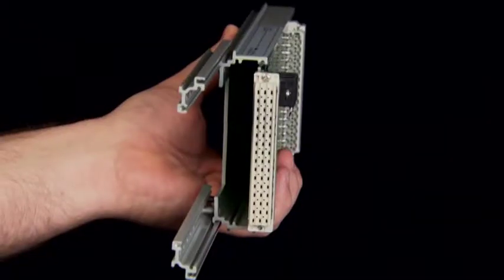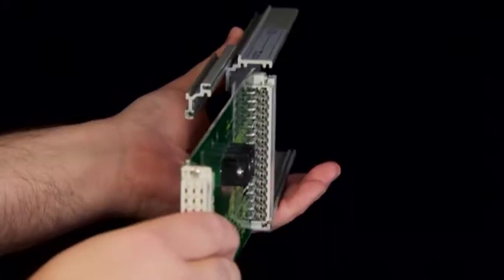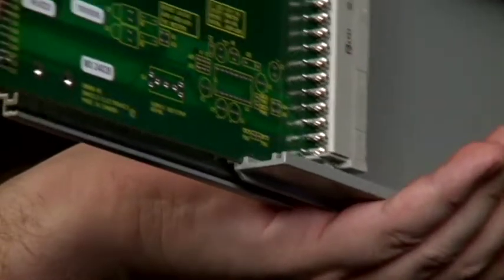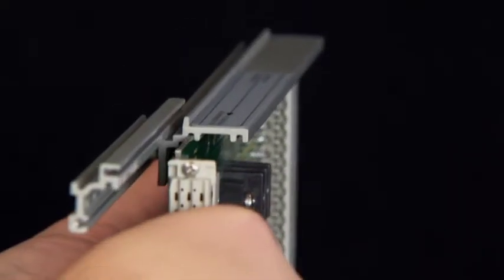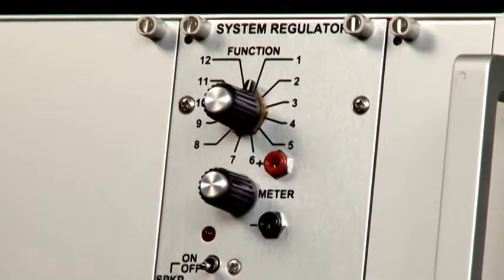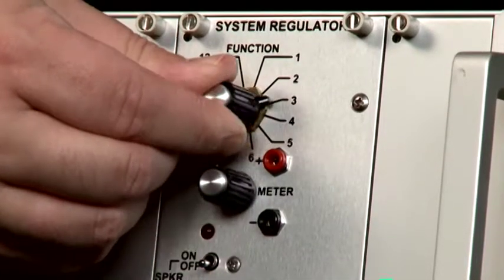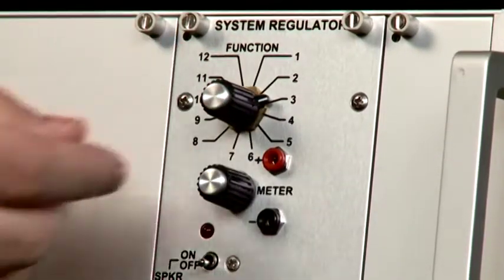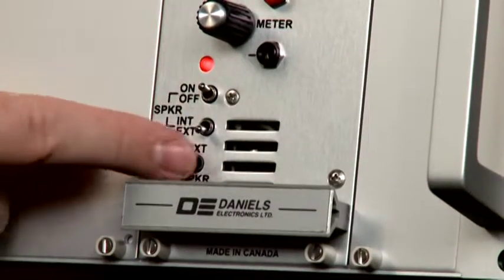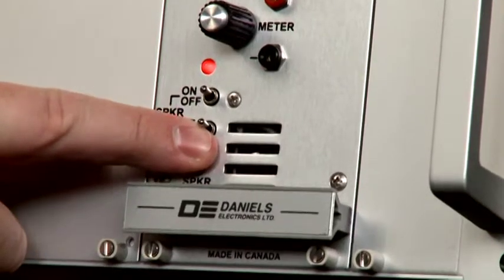Connect the receiver to the sub rack using an extender card. Ensure that the extender card is inserted in the inside rail of the extrusion for the receiver. The outside rail is for the transmitter. Turn the system regulator function rotary switch to position 3 for receiver A and position 5 for receiver B if used. Turn the speaker switch on and ensure it is set for internal speaker.